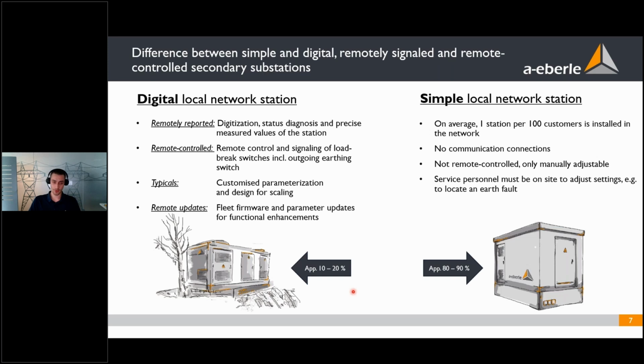Yeah, as I said before, from a technical point of view, 100% digital local network stations would be perfect, but from an economical point of view, 10 to 20% are sufficient, and the rest would be simple local network stations. The features of these stations are that on average, you have one station per 100 customers installed in the network. These stations do not have communication connections. They are not remote controlled and only manually adjustable. And that means that service personnel has to be on site to adjust settings or to evaluate earth fault or short circuit location.